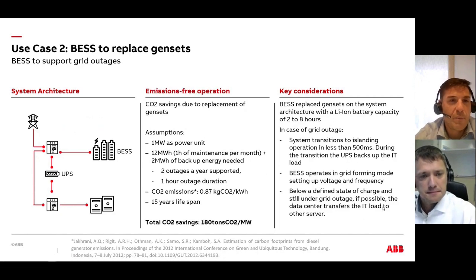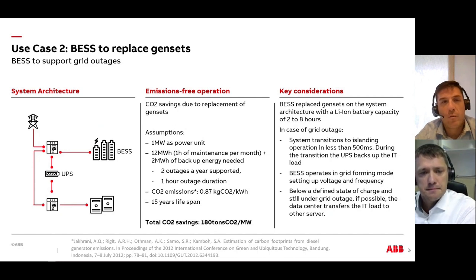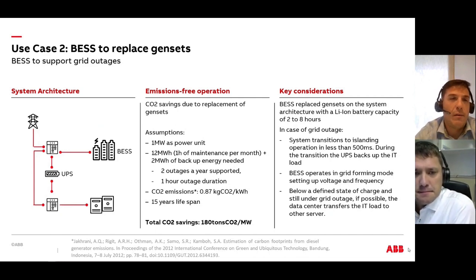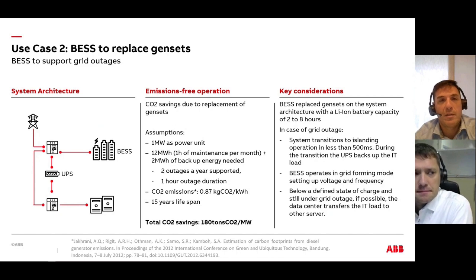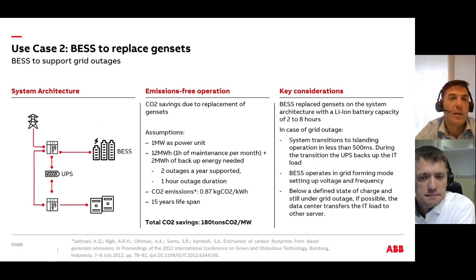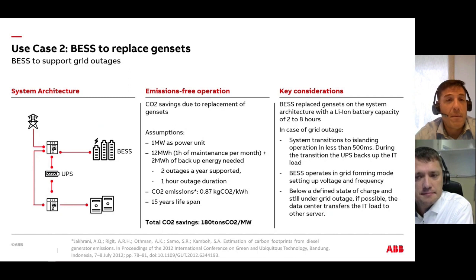So in use case number 2, before we were putting the BESS in parallel with the gensets and reducing the time that these are going to operate, just covering those short outages. In this use case number 2, we put the BESS to replace the gensets fully. Savings are much longer because the gensets will not run even for maintenance. So we have a total saving of 180 tons of CO2 per megawatt.